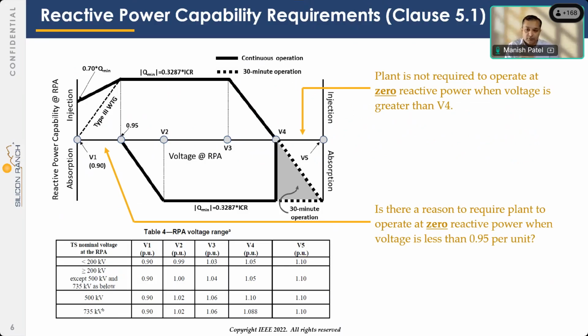All right, so the previous two figures that you saw were active power versus reactive power. Pretty simple. Well, for what voltage does that relationship apply? So that is specified with this figure and a lot of words to go along with it. What this means is when the voltage is greater than V4, so if you come down in this table and look at the V4 ranges, they're usually high, 105% all the way to 110%, right?